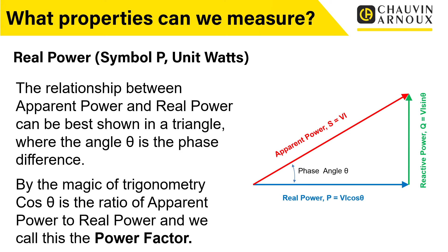We also talk about reactive power, given the symbol Q, with unit VAR, volt-amps reactive. In a purely resistive circuit, or one with a balance of inductance and capacitance, apparent power and real power are the same, and the power factor is perfect, or 1. There's no reactive power; apparent power and real power are aligned, and we've got no waste, for want of a better term.